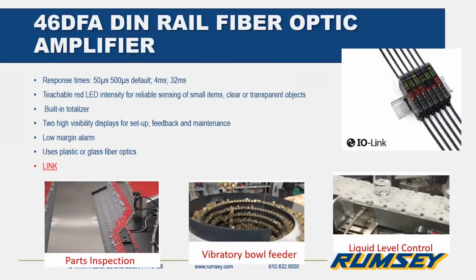The 46DFA DIN rail fiber optic amplifier, once again, IO-Link capable. The standard response times are 50 and 500 microseconds as a default, but you can extend out the output to 4 milliseconds or 32 milliseconds. It has a built-in totalizer, a low margin alarm, 2 high visibility displays for setup and feedback, and a teachable red LED for intensity levels, so you can sense small objects or clear or transparent objects. And it uses both plastic and glass fiber optics.